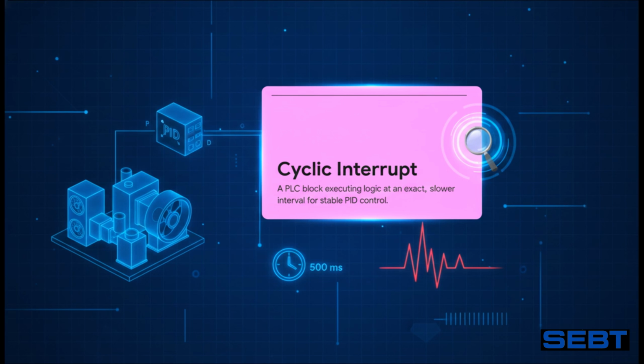But sometimes running as fast as physically possible actually isn't what we want. Enter the cyclic interrupt. This is a highly specialized organization block inside the PLC. So instead of running every single millisecond, you can actually tell the PLC, hey, run this specific block of code at a perfectly exact but slower interval, say exactly every 500 milliseconds. Now you might be wondering, why does this even matter for HVAC? Well, complex math like PID temperature control needs a steady, precise time delta to calculate correctly. If you try to evaluate a temperature loop every single millisecond, the mathematical adjustments will just go completely erratic. By safely placing our PID logic inside a cyclic interrupt, we get incredibly stable, smooth control over time.